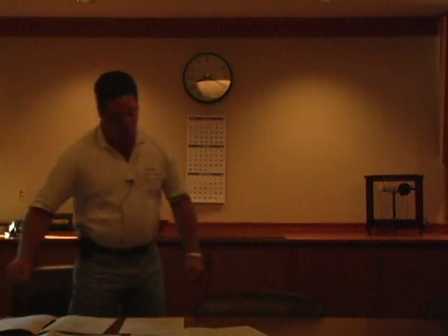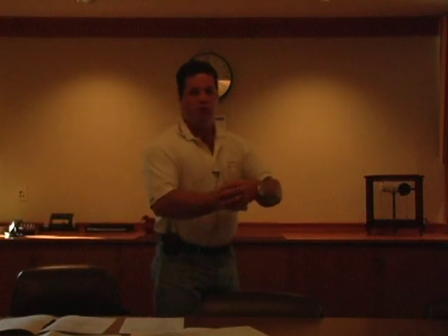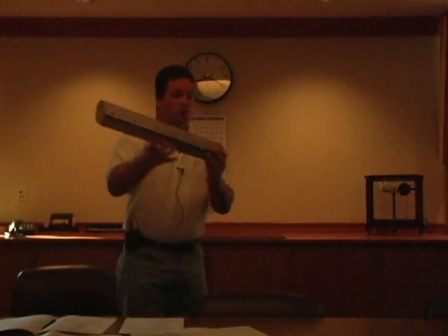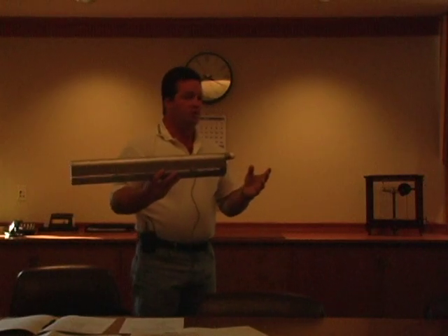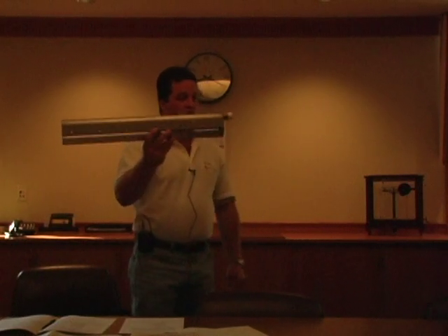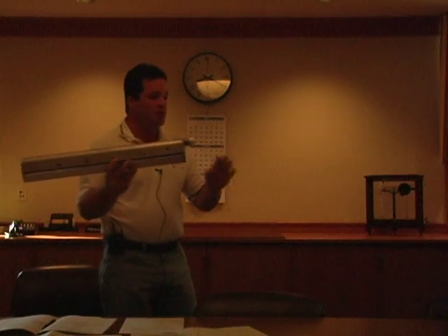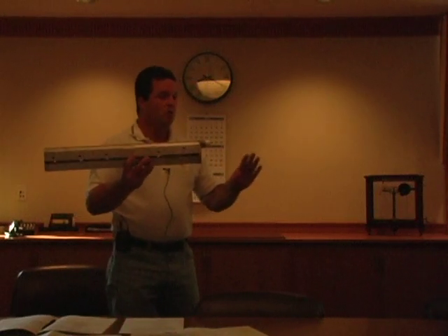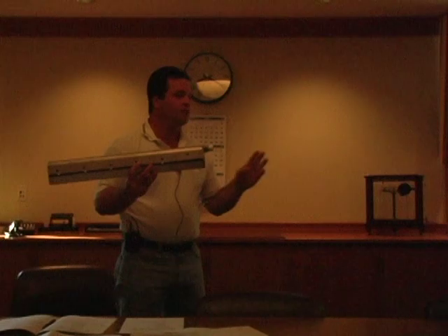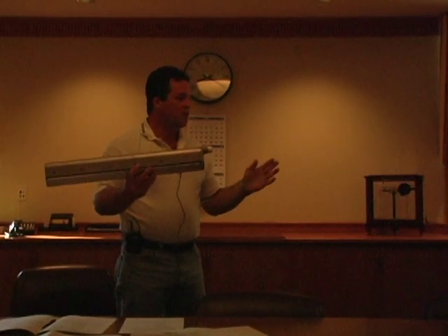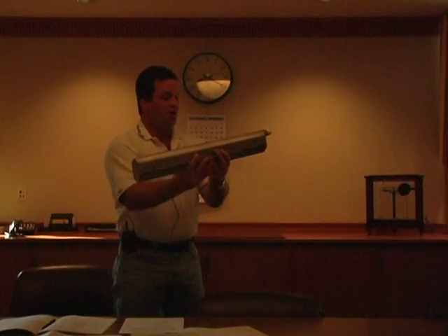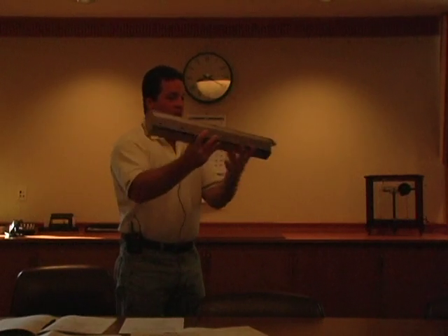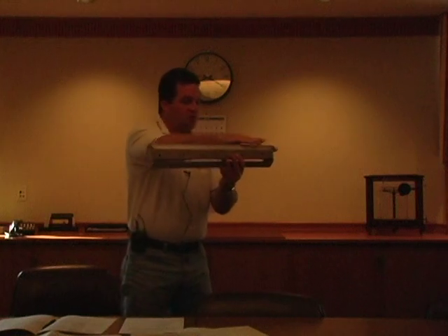As far as any kind of pipe repair procedures, say if someone comes into the tank itself and accidentally steps on one of these and bends it, okay? That would be considered the equipment being damaged, because what we're trying to accomplish is this system being level, plus or minus a quarter of an inch. The reason being is air wants to come out the least path of resistance. So say if this got bent a little bit, all the air is going to come out the higher end of the diffuser, where we want it throughout the whole surface itself.